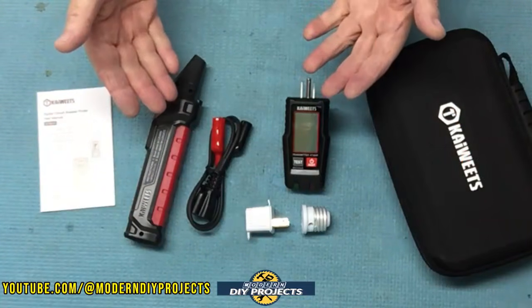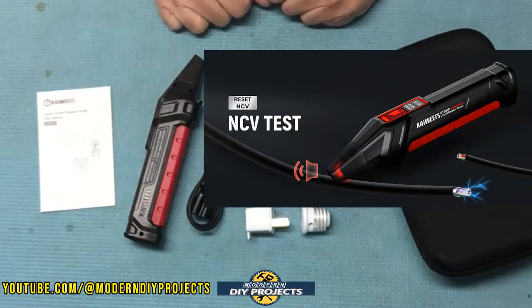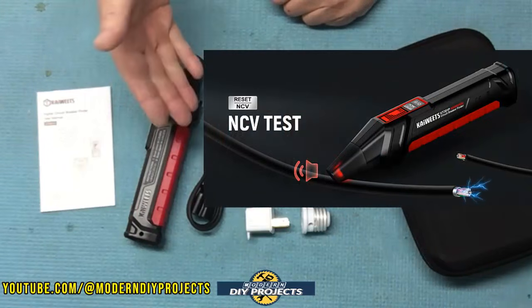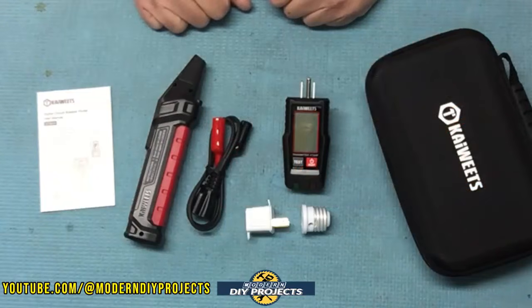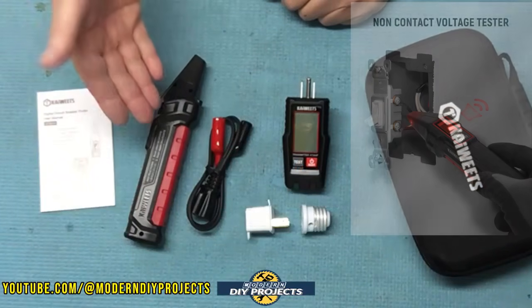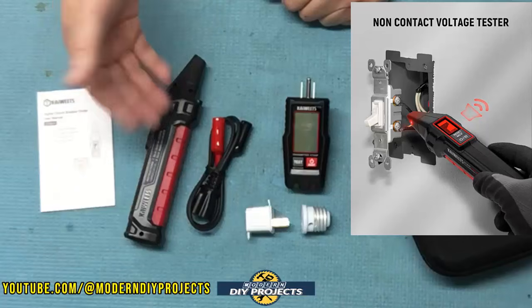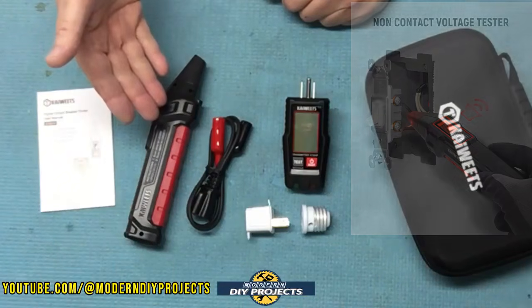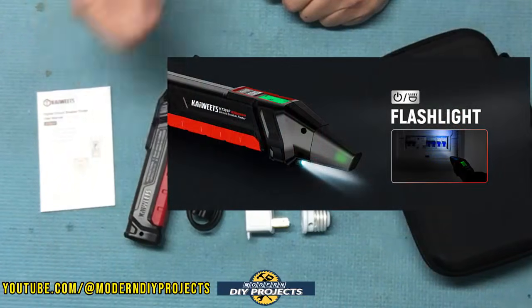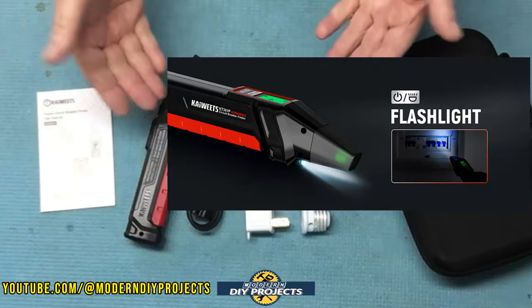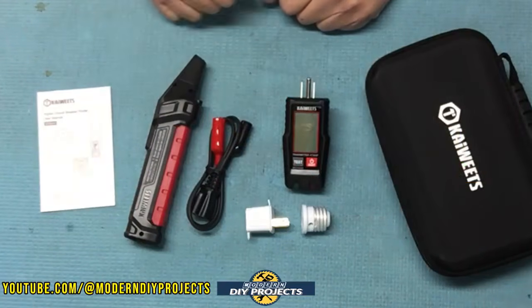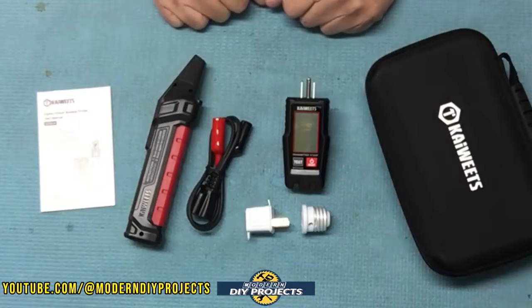This unit has an operating voltage range of 30 to 150 volts and has a Cat 2 300 volt rating. The receiver unit not only works as a receiver when locating the correct circuit breaker, but it also has a built-in flashlight for working in dark circuit panels, and it works as an NCV, or non-contact voltage tester, for the rest of your testing.